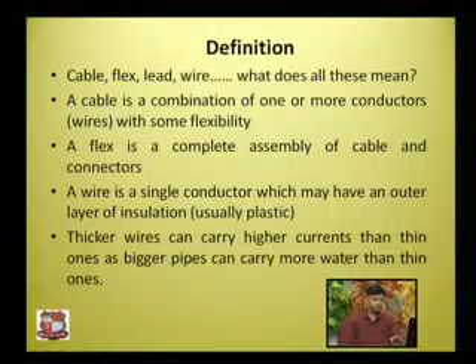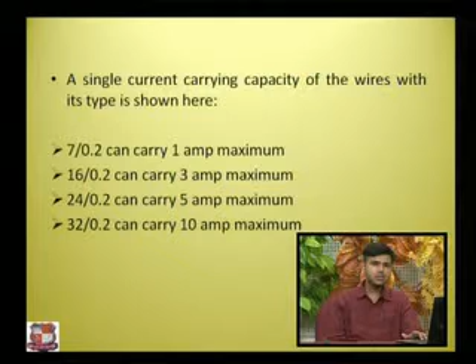Okay, this is the current carrying capacity of wires by type. I have taken this data from one of the good magazines. So if it is written like 7 by 0.2, it means 7 strands of wire with a diameter of 0.2, and it can carry 1 ampere maximum current. Similarly, if it is written 16 by 0.2, it can carry a maximum of 3 amperes. So it is 16 strands of wire with 0.2 mm diameter, and 24 by 0.2 can carry a maximum of 5 amperes current.